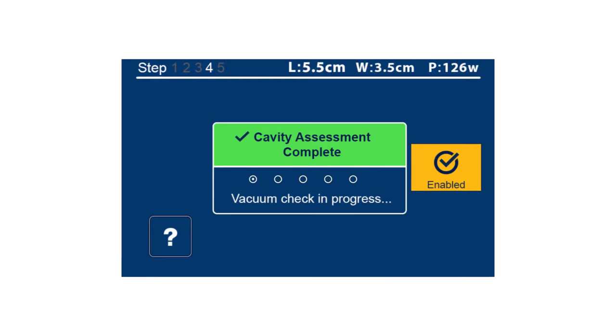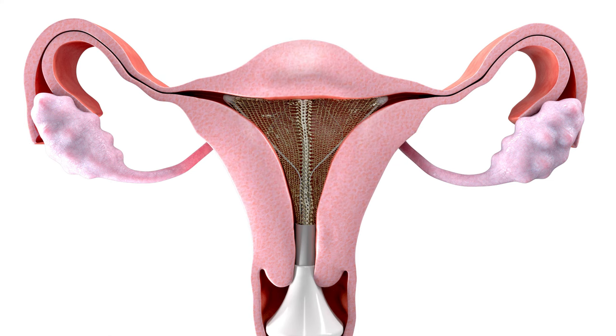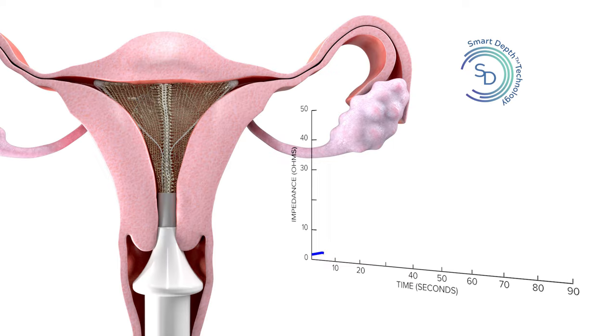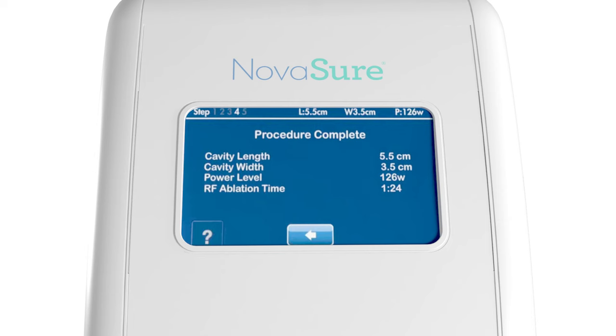You may now press the foot pedal to begin the ablation. The moisture transport system suctions the uterine cavity onto the NovaSure array. Once the RF energy treatment begins, RF on and the timer will appear on the blue screen on the NovaSure controller. The NovaSure procedure features smart depth technology, which continuously monitors and measures tissue impedance to ensure a customized and reproducible depth of ablation — the only GEA designed to terminate upon reaching a scientific endpoint of 50 ohms of impedance.